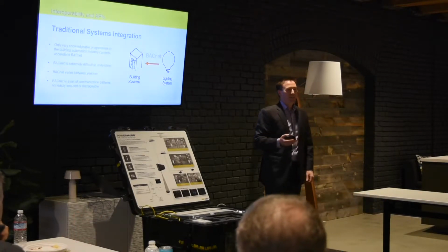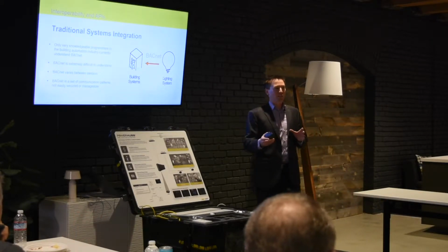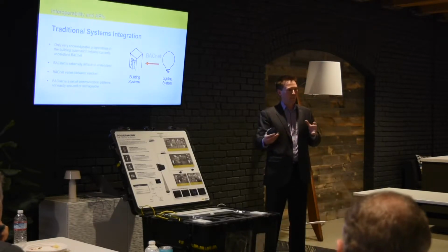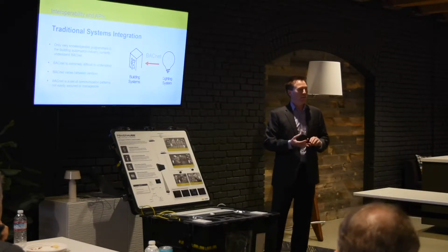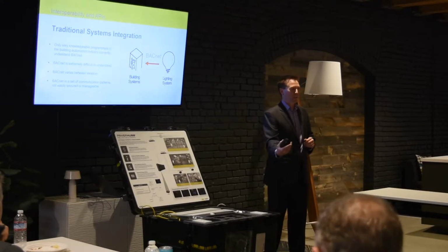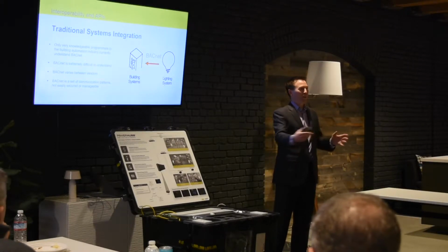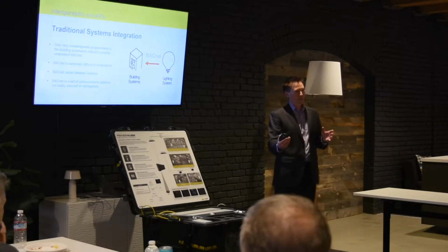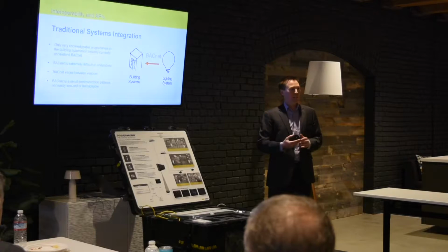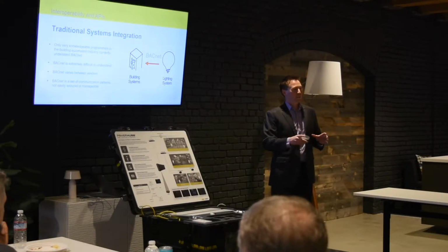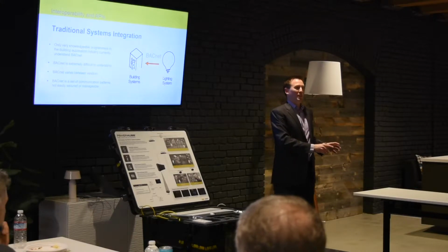It's pretty good. And BACnet is an interesting network. There is no security on it at all, and it's used for HVAC systems typically, and possibly other systems to talk to each other. But there's no security. It's all peer-to-peer. So when you have peer-to-peer, if someone gets on the network, they can see everyone else, and there's no real way to stop that from happening. One bad actor could really start compromising others. So there's a lot of issues with BACnet, and it was really not meant to be on the network.